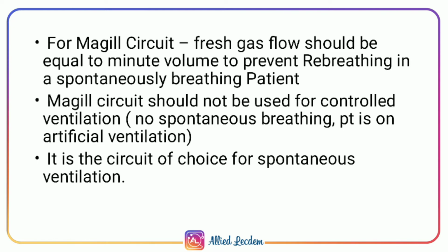For McGill's, fresh gas flow should be equal to minute volume. Minute volume is nothing but the amount of gas inhaled or exhaled by a patient in 1 minute. McGill circuit is not recommended for controlled ventilation. Controlled ventilation is when the patient is not breathing on his own and the ventilator will take over his respiration.